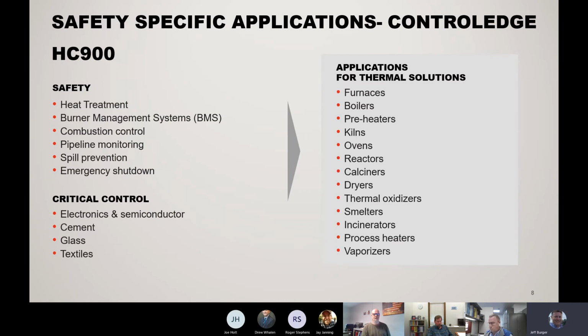Some of the safety applications are in heat treatment, burner management systems, combustion control, pipeline monitoring, spill prevention, and emergency shutdown. Like I said, a lot of the applications where the HC900 really shines are furnaces, boilers, preheaters, kilns, ovens, reactors, dryers, and thermal oxidizers. So there are a lot of thermal applications that it plays real well in. A lot of the critical control applications are in electronics, semiconductors, cement, glass, and textiles.